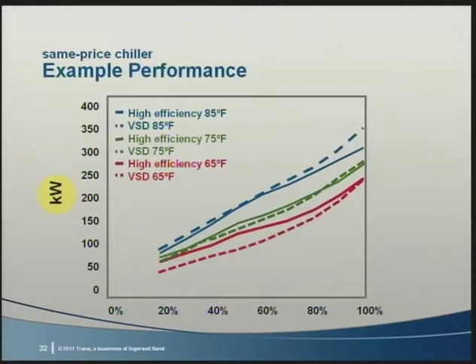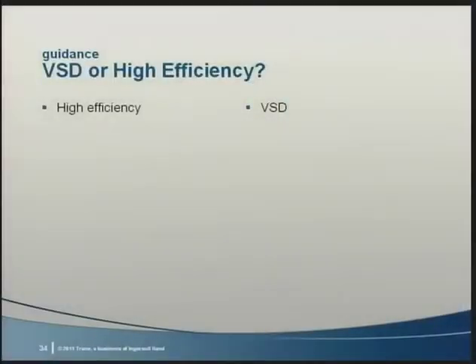Some observations. At condenser water temperatures near design, the constant speed chiller is more efficient, the area shown here in yellow. At low condenser water temperature, or low lift, the variable speed chiller is more efficient, the area shown here in blue. So which makes more sense? Again, we need to perform an analysis that accounts for all of the loads. As the rating standard states, IPLV is not to be used as a surrogate for energy analysis. Consider the high-efficiency chiller when you have significant demand charges or in humid climates.